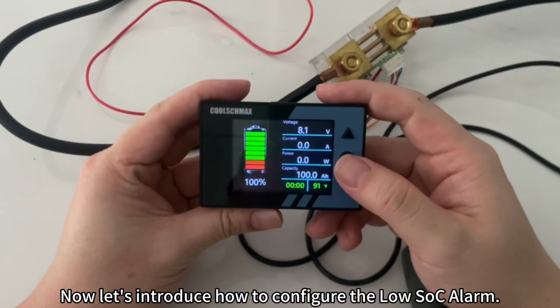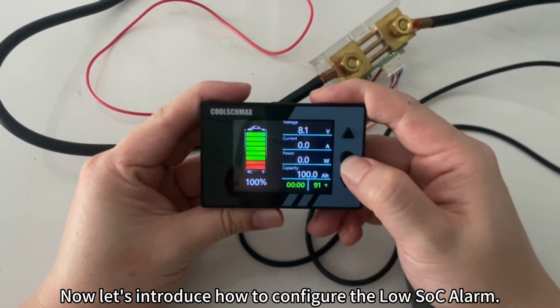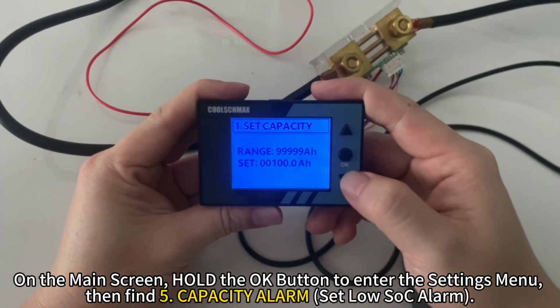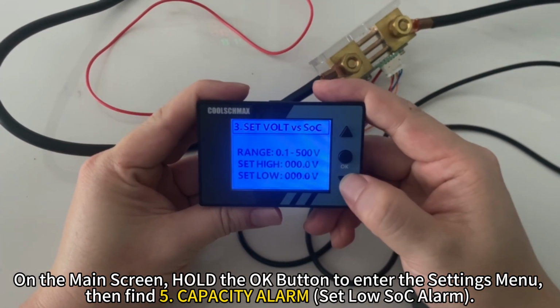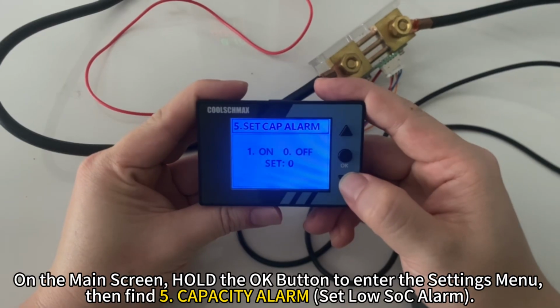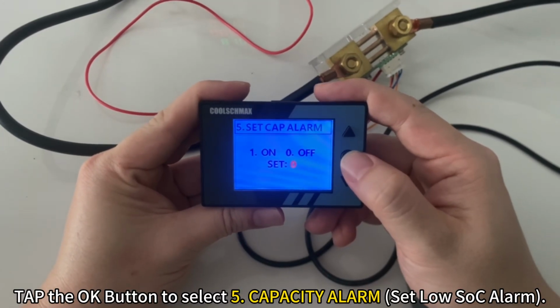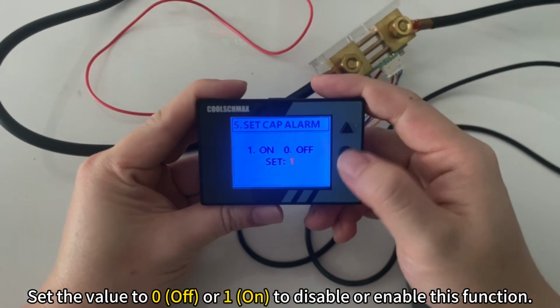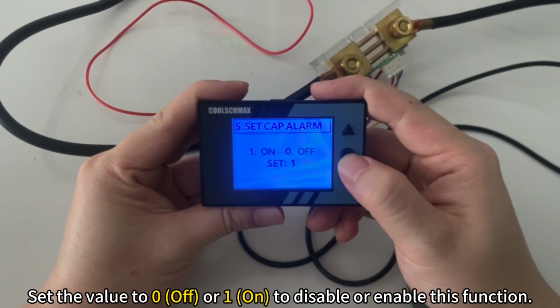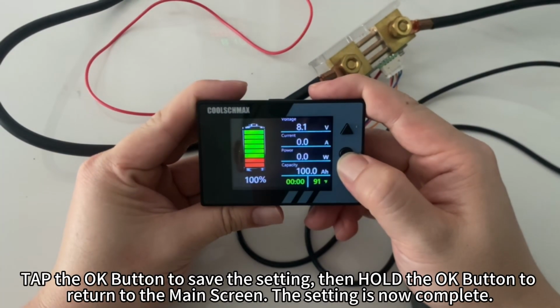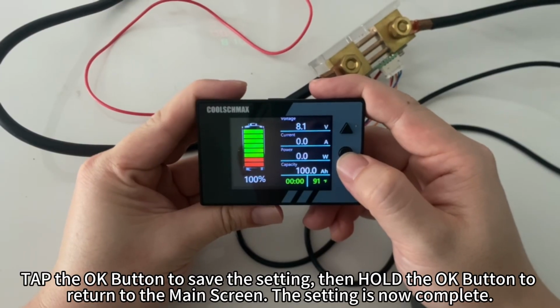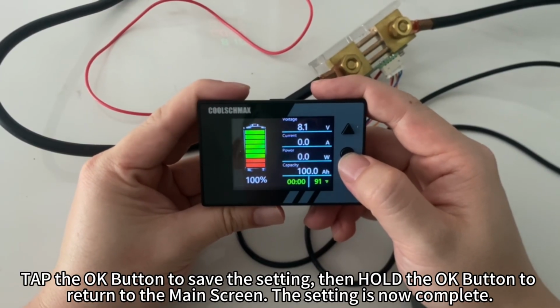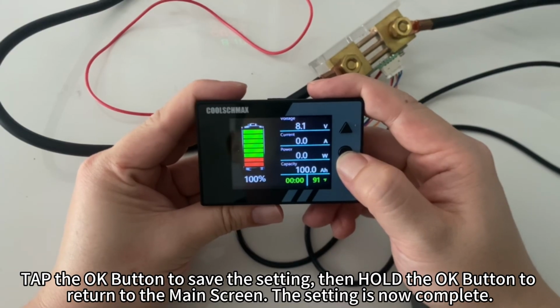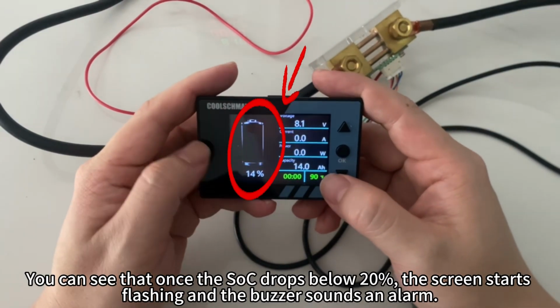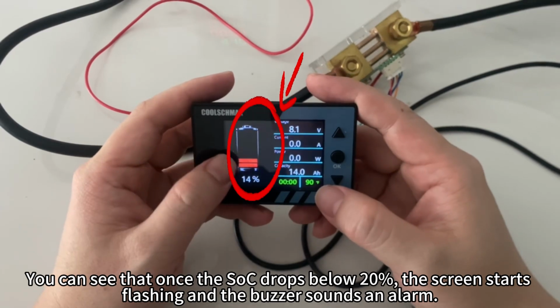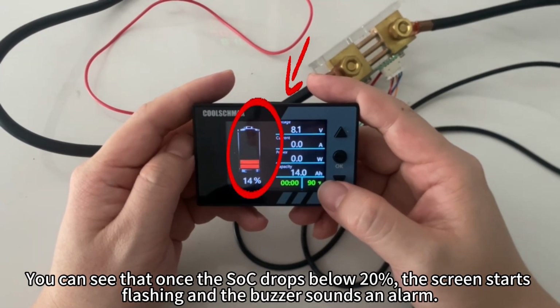Now let's introduce how to configure the low SoC alarm. On the main screen, hold the OK button to enter the settings menu, then find 5. Capacity alarm. Tap the OK button to select 5. Capacity alarm. Set the value to 0 or 1 to disable or enable this function. Tap the OK button to save the setting, then hold the OK button to return to the main screen. The setting is now complete. You can see that once the SoC drops below 20%, the screen starts flashing and the buzzer sounds an alarm.